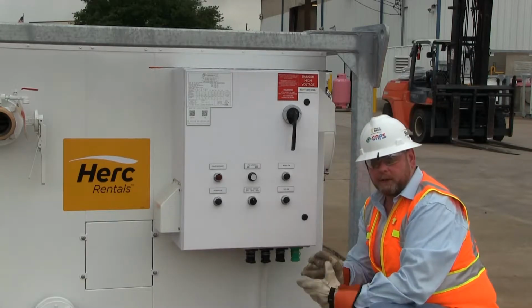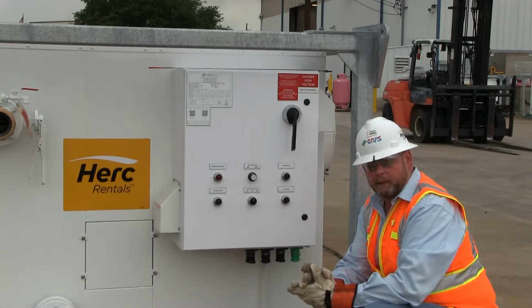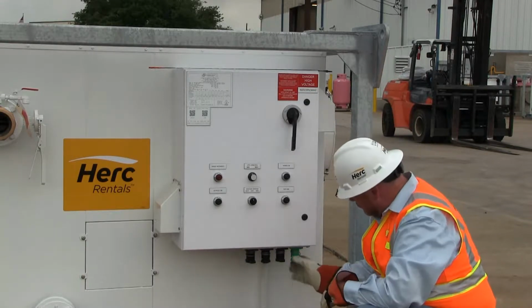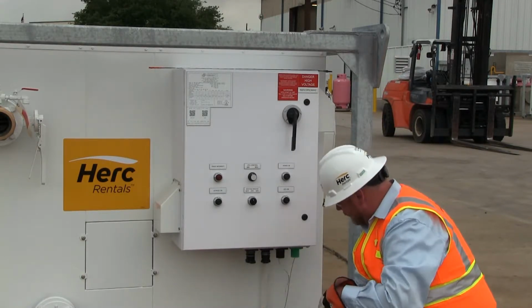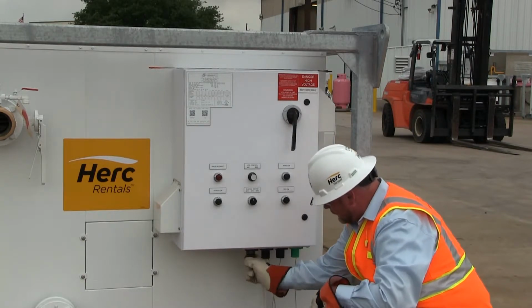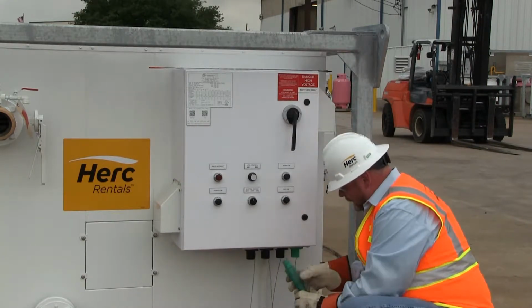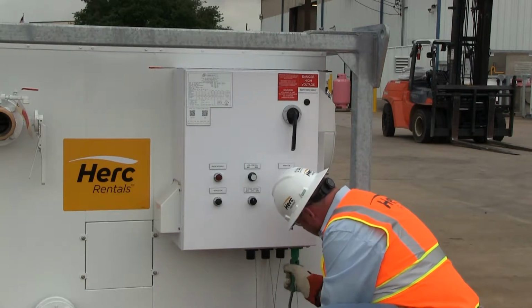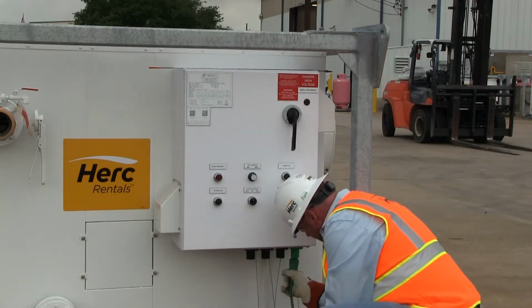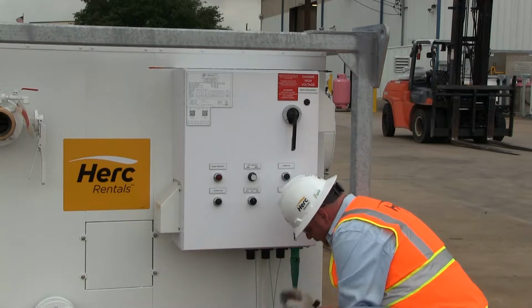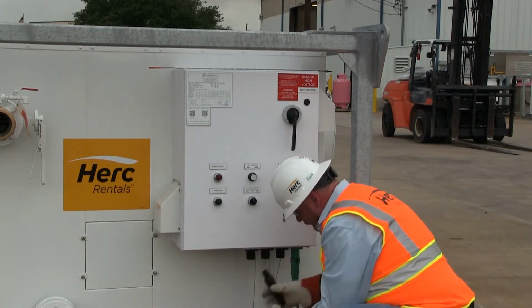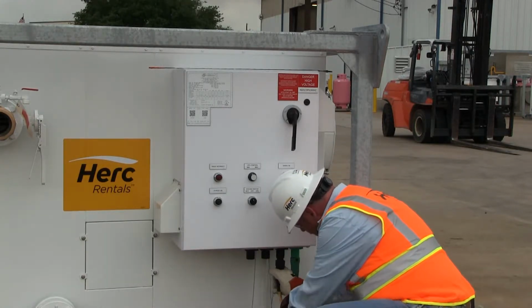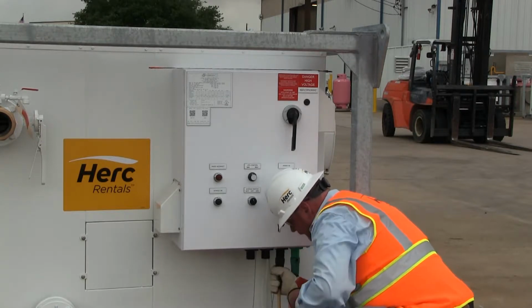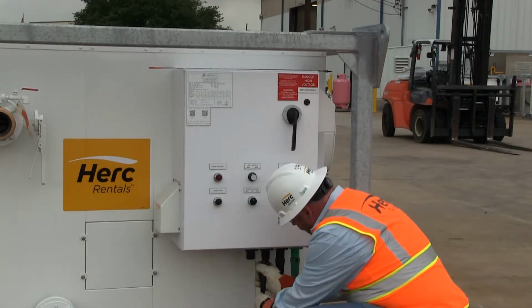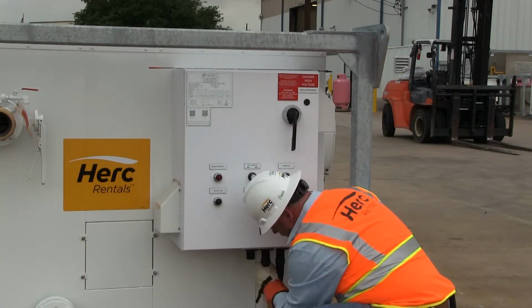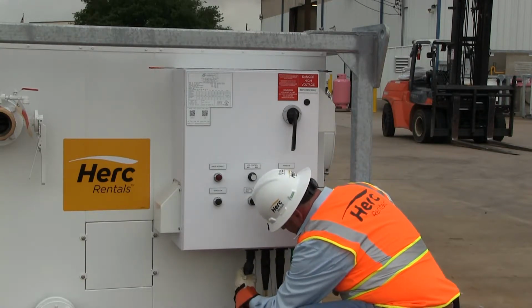The next step is going to be to hook up our high voltage temporary power to the 50-ton air handler. First thing we're going to do is remove the dust and moisture caps off of our cam lock connections at our main control panel. The first lead you always hook up is going to be the ground lead. You want to make sure the machine's grounded in place before you hook up any of the other L1, L2, and L3. And we're simply just going to go in and plug in our male by female cam locks to the L1, L2, and L3 connections at the chill water air handler.